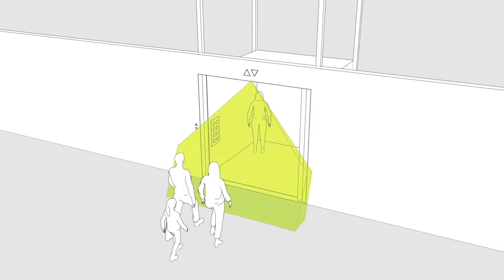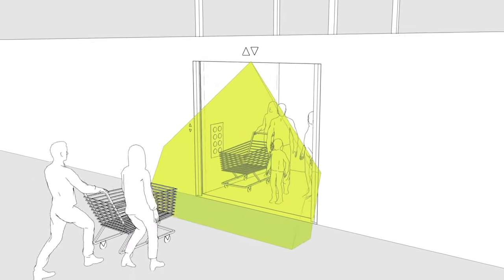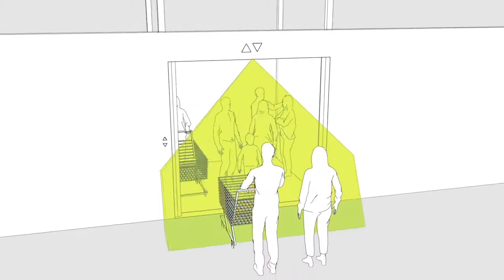The Capsafe 3D time-of-flight sensor is used to detect the presence of approaching objects in accordance with code requirements. This sensor monitors the area in front of the elevator cab opening and captures 9,600 discrete points of distance information 20 times each second. This distance information is then used to analyze changes occurring in front of the elevator cab entrance. Objects approaching the elevator cab are communicated to the Capsafe controller, while stationary objects are ignored after a short time so that plants or luggage won't hold the elevator from servicing other calls.